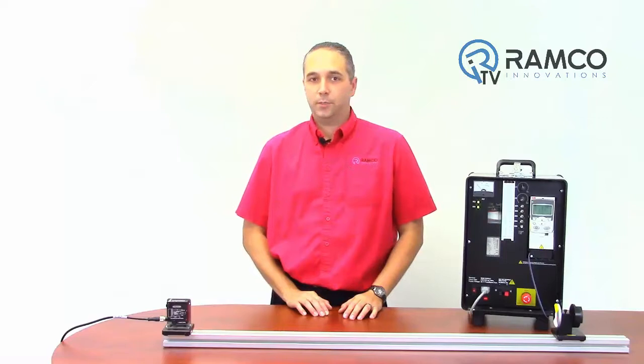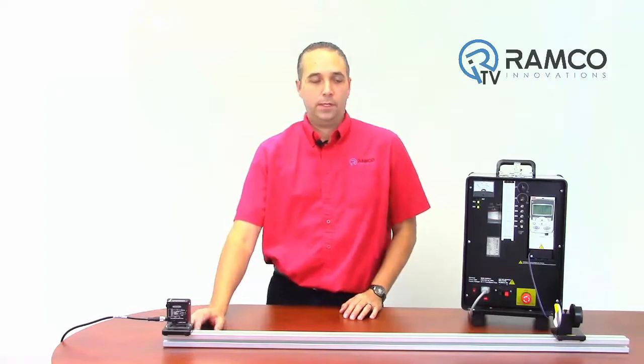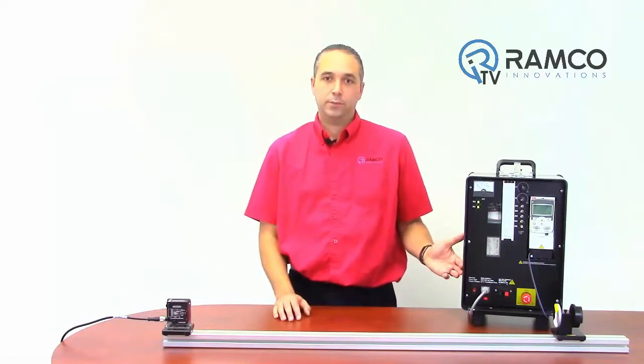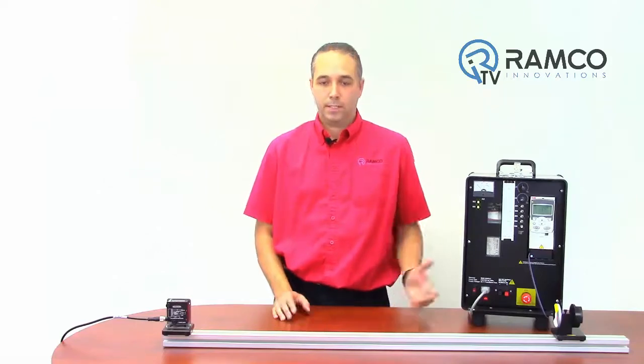For this demonstration we'll be using the LE550 laser measurement sensor from Banner. The sensor has a 4 to 20 milliamp output. The ACS355 has two scalable analog inputs capable of reading negative 20 to plus 20 milliamps or negative 10 to plus 10 volts. Let's get them to work together.